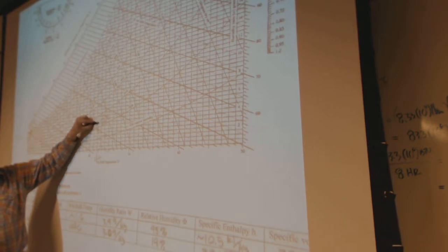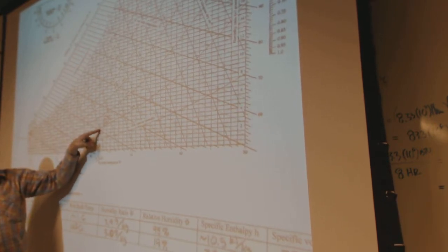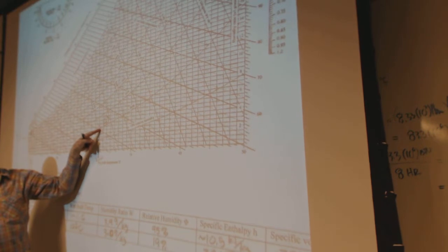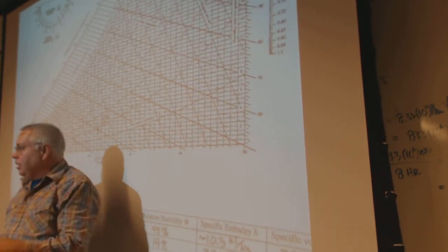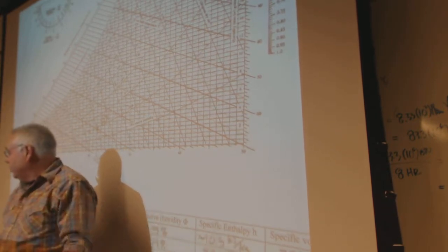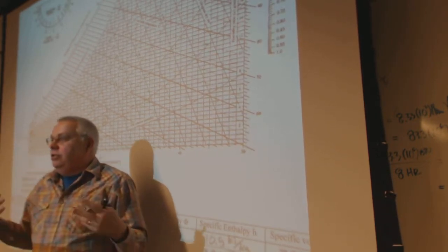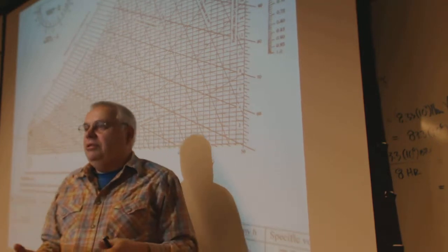And what this tells me is this air was heated up when it was really cold outside, so they're not spending a lot of energy exchanging all the warm air for cold air just for the hell of it. So we're still dealing with the moisture in the air like it was when it was 20 degrees outside.